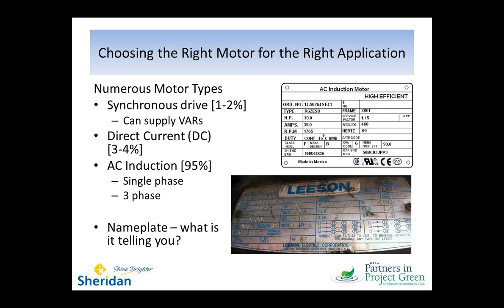The next thing you probably want to find out here is the service factor. That's the number I mentioned first, 1.15, and that essentially says you've got a 15% margin, and you could drive this a bit higher. You drive it with a bit more load, and it will be perfectly happy. It won't climb out of its maximum temperature range. This is not something you'd want to do for a prolonged period of time, but if you had a bit of a surge or a bit of an overload, it could certainly handle that within that period of time.